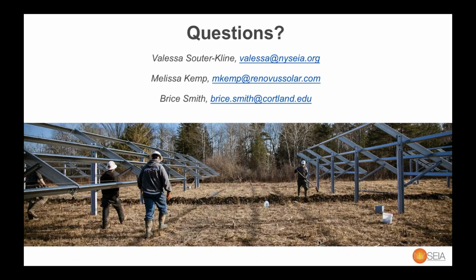In addition to those questions, if you were to exceed the minimum load on a circuit, or if the circuit was the dominant circuit for a substation, there are other questions that may come up in a CESIR study, where if you begin to have questions around what Melissa mentioned, the working group is looking at backfeed into the substation, how much of the substation load you are likely to carry. In that best practice document that the working group is working towards, and in other ways it's going to publish and publicize its considerations, there are fractions of that substation load that will then trigger some high-cost upgrades depending on the configuration of the substation. So it's not easy to answer as a single question.